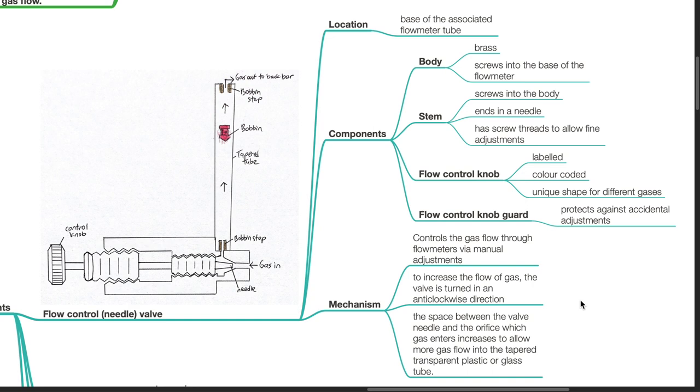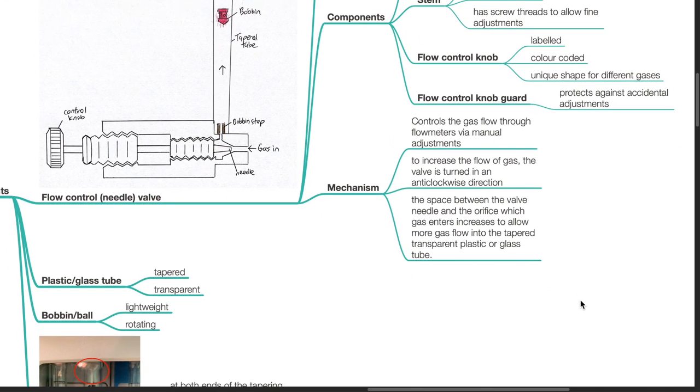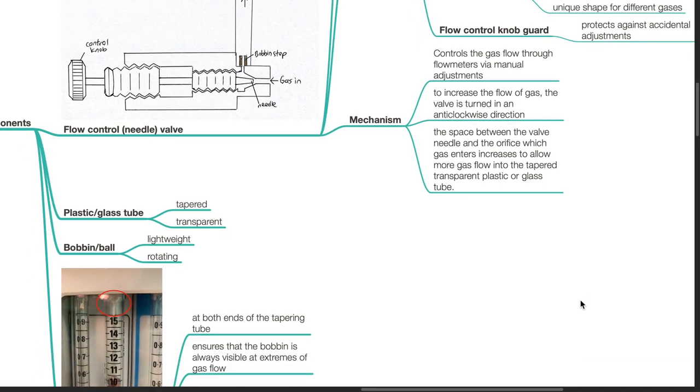Mechanism: It controls the gas flow through the flow meter via manual adjustments. To increase the flow of gas, the valve is turned in an anti-clockwise direction. The space between the valve needle and the orifice which gas enters increases to allow more gas flow into the tapered transparent plastic or glass tube.